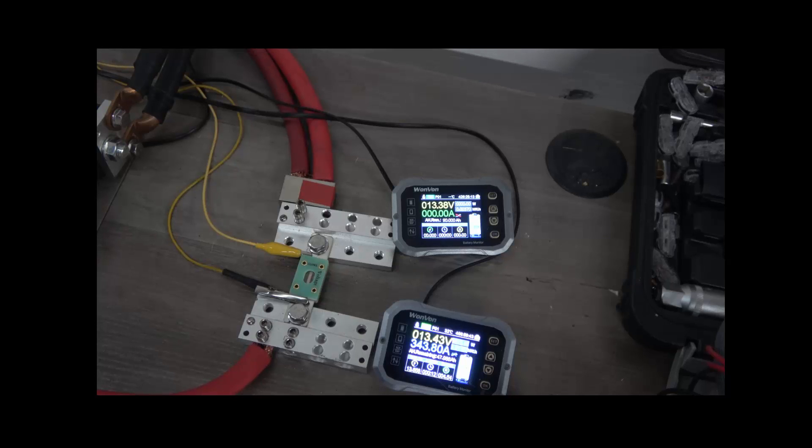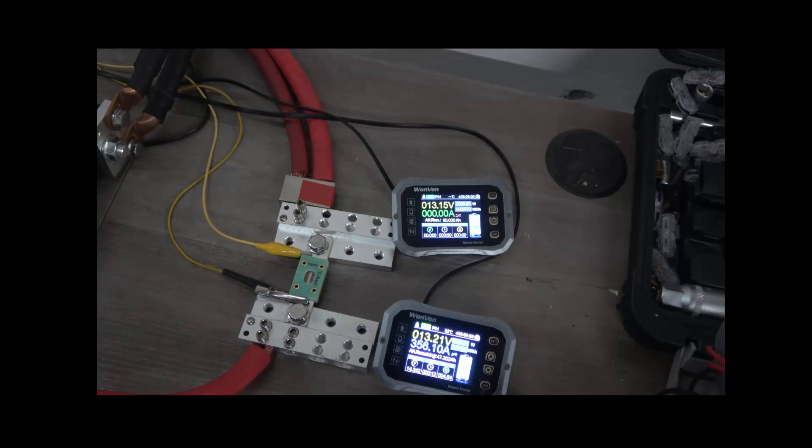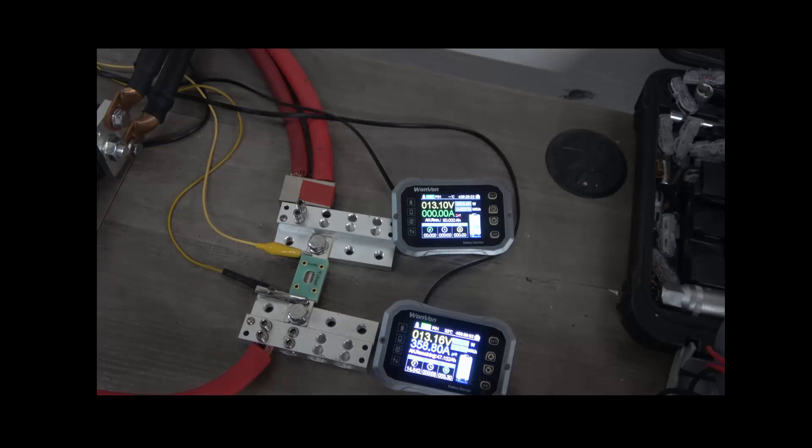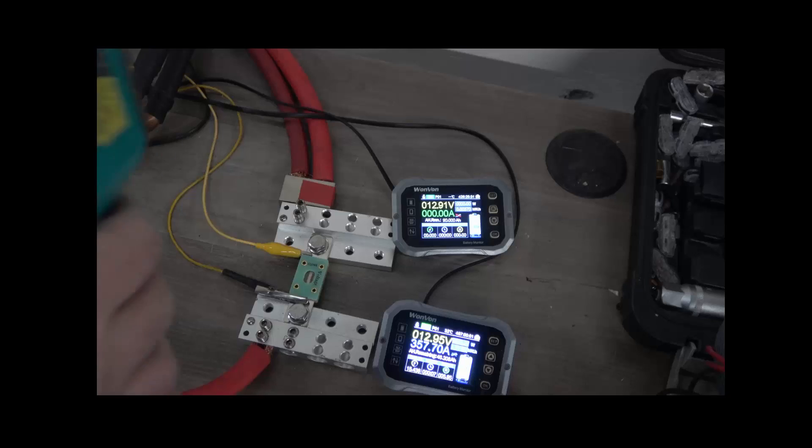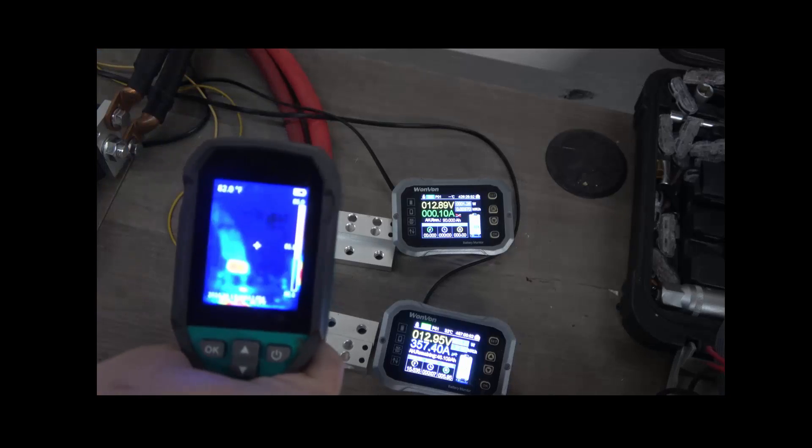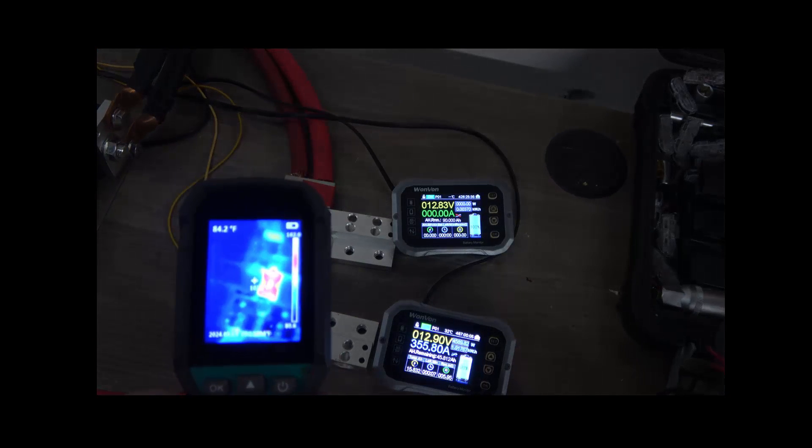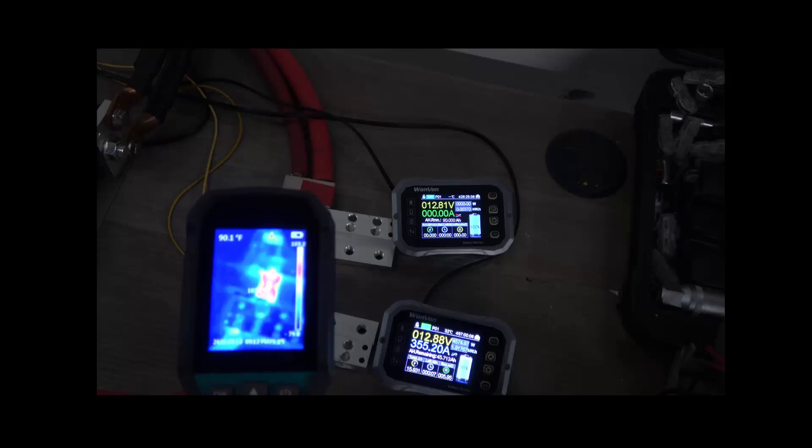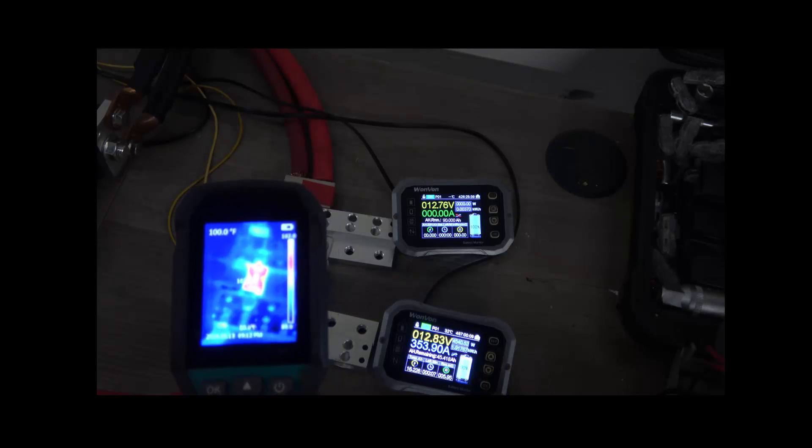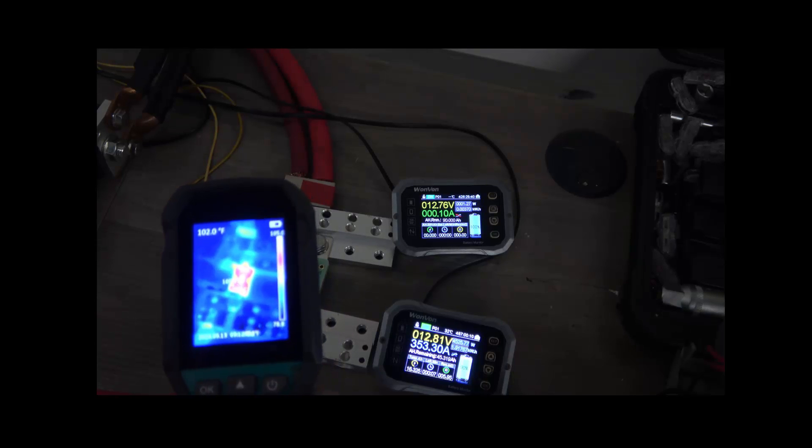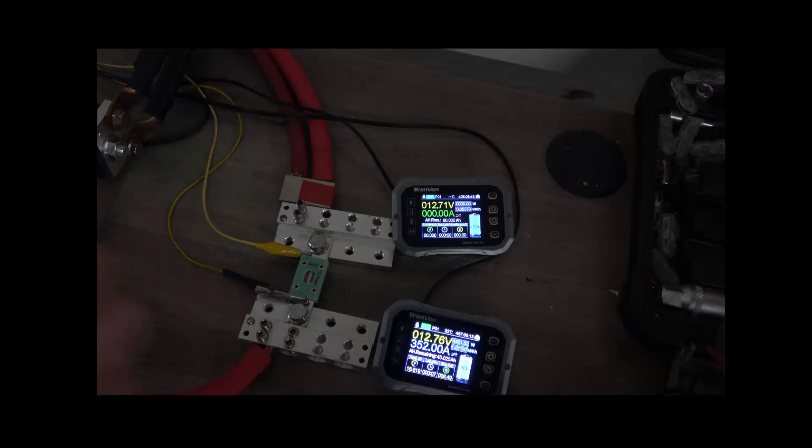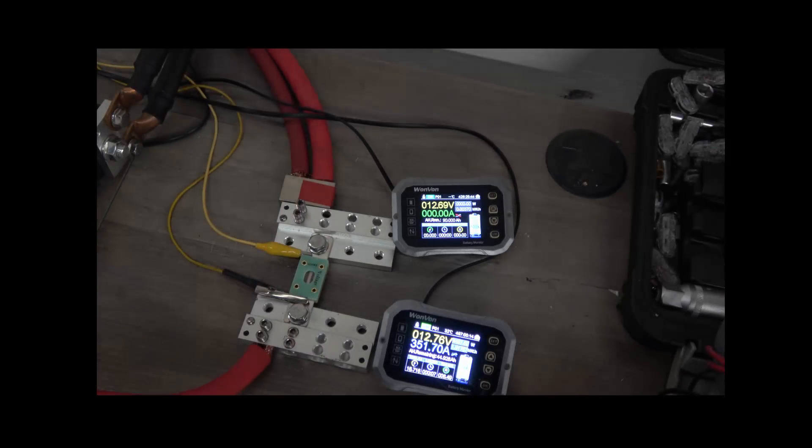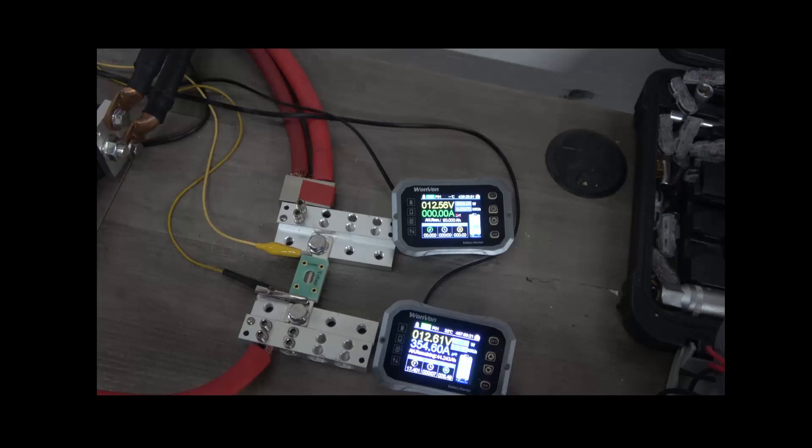So we have less than 0.1 volt drop at 300 amps through this fuse. And our temperature on the fuse is 95 degrees. You're going to see it is red, but that's just because it's the hottest thing on the screen, but it looks like it's hanging out at about 104 degrees. And as you can see, it's just chilling. As far as voltage drop through the fuse, we are still less than 0.1 volt.